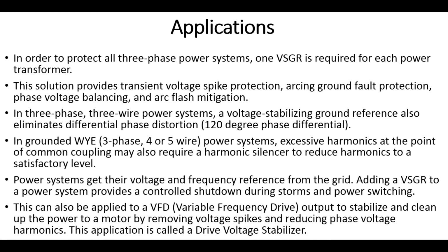Also, with all of this noise, there's an approximate 100-foot maximum length of this power cable because of something called standing wave or reflected wave, basically the harmonics and spikes causing a problem in the wiring between the motor and drive, causing the drive itself to fault.